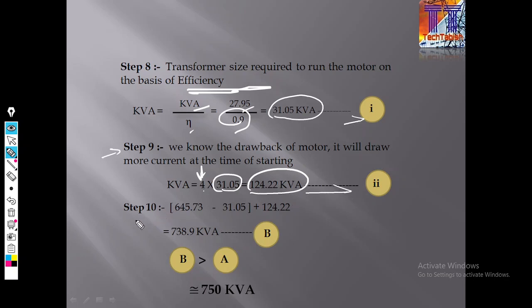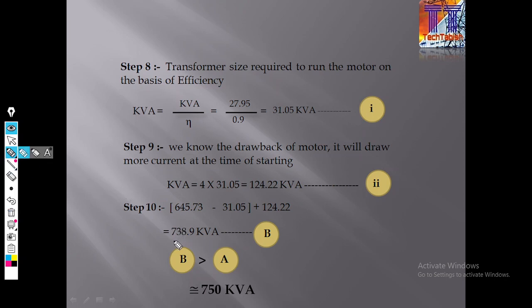Now what we have seen, the total connected load kVA rating is 645.73, from which we have to subtract the motor which we have taken individually. Because this already includes the continuously running motor, we have to subtract it, and after that we have to add this. Why? Because it takes 4 times the power. If we run this continuously running motor, it will take 4 times higher power. That's why we have added this. After doing all this, the result is 738.9 kVA. We have denoted this with B.